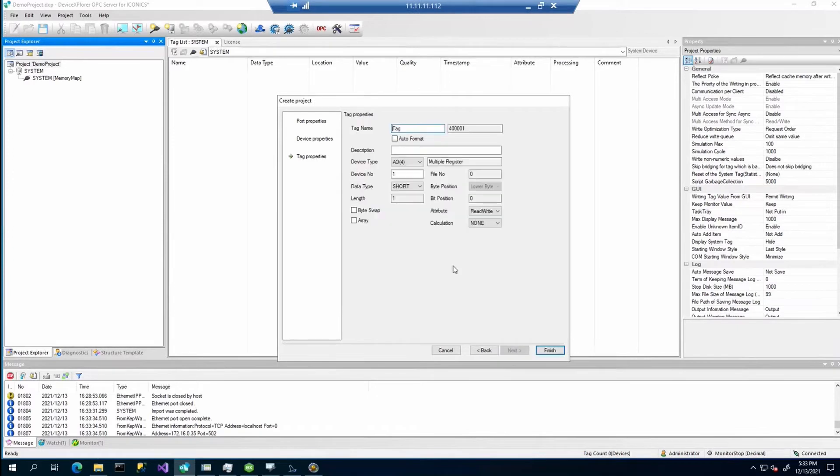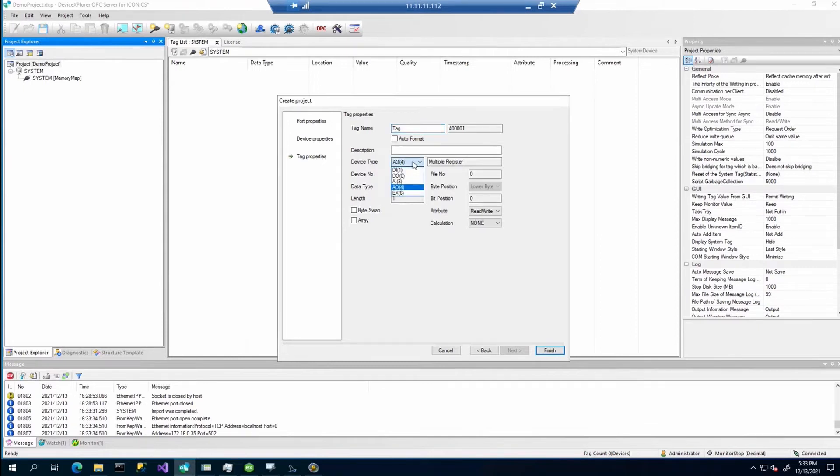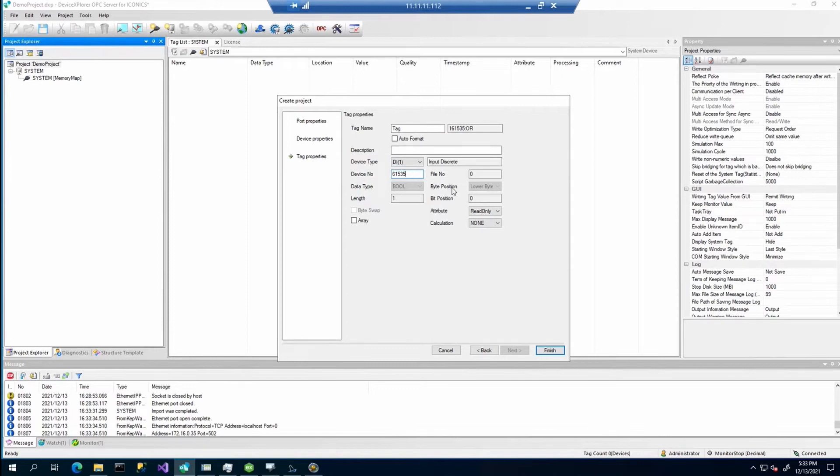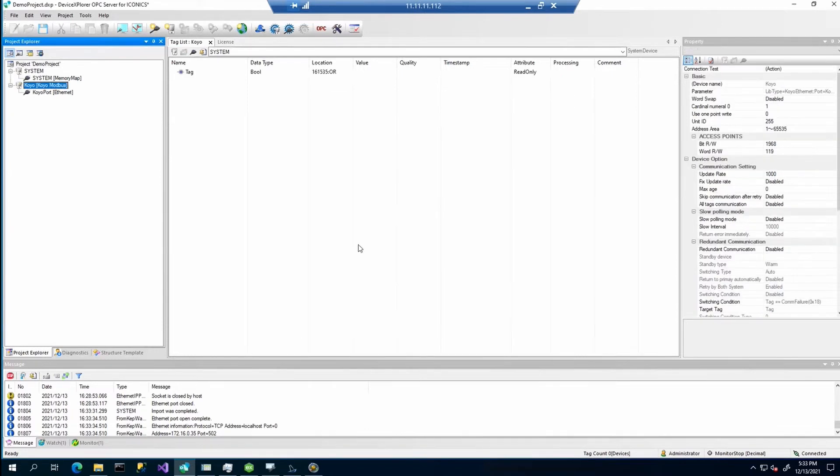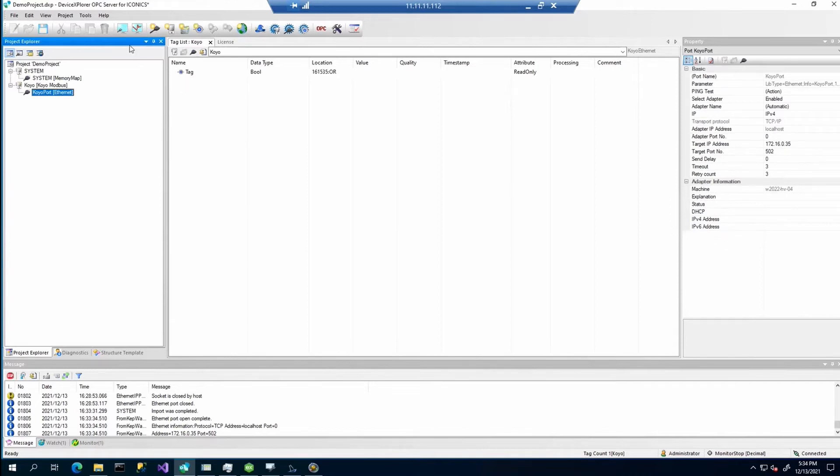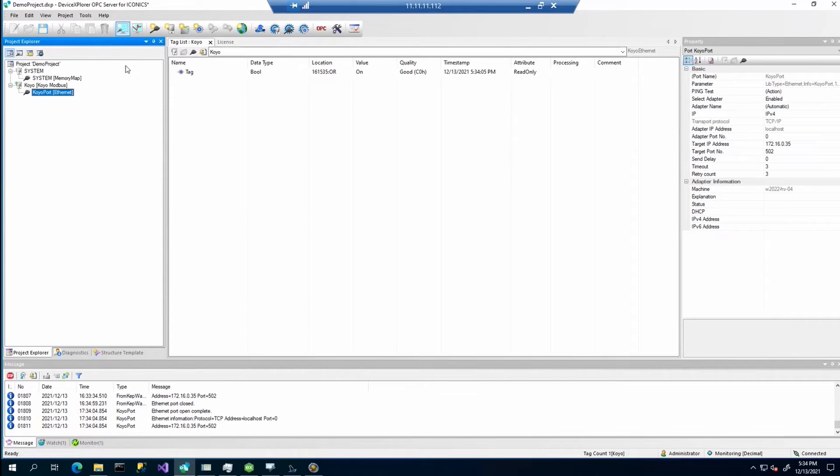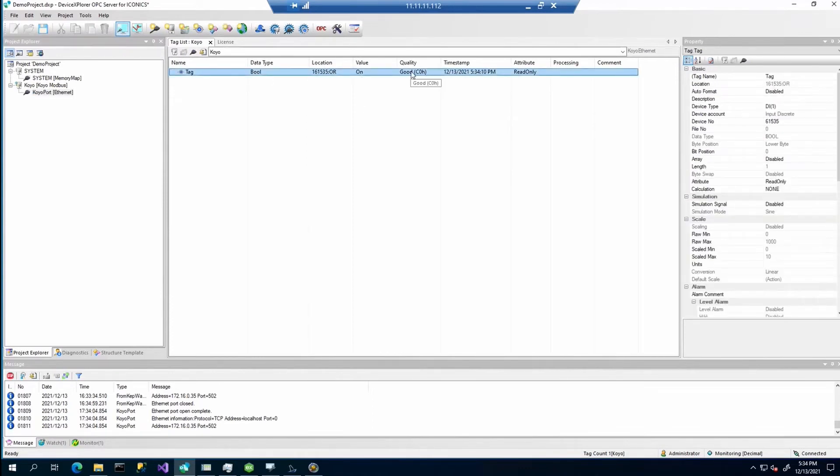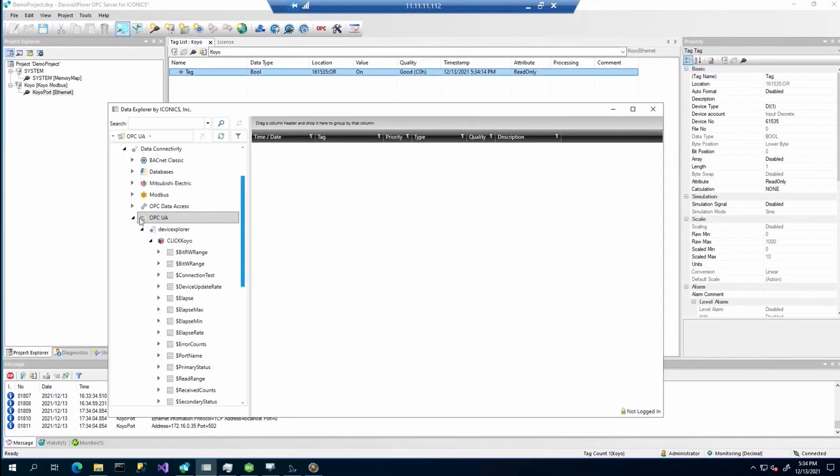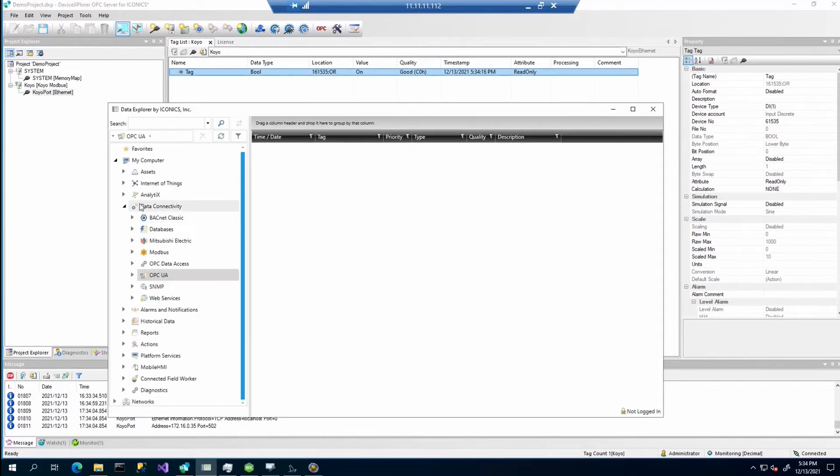Here we need to specify the address area and again you can do the connection test and everything is OK. In the last step we can set some tag which will be connected to that device. So I have one prepared. You will enter the device type, device number and so on. You can click finish and it will create the project with that tag. There is the functionality that you can immediately monitor the created tags. You can see that we are connected, the communications OK and the value is on.